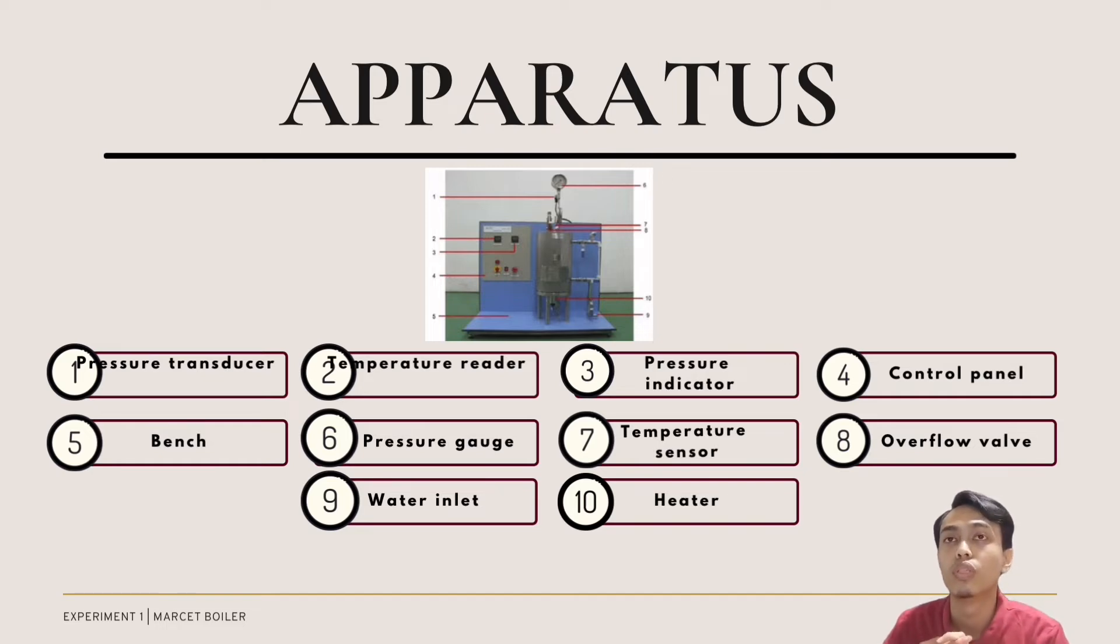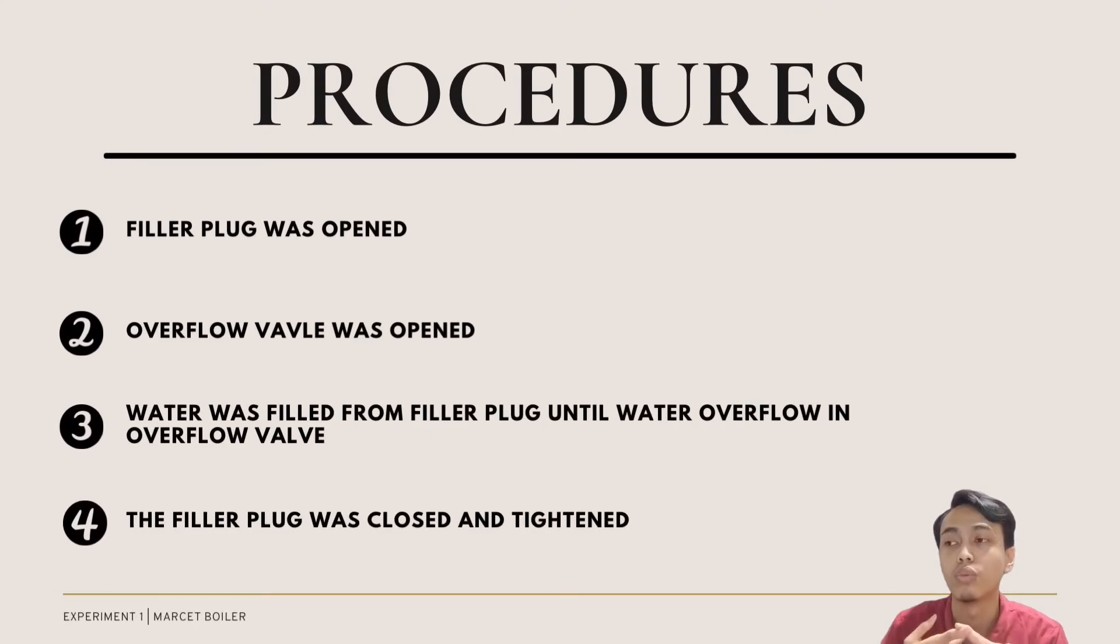Then, we move to the procedure. The first step: open the filler plug with the spanner. Second, open the overflow valve. When both are open, fill the water from the filler plug until the water overflows in the overflow valve. Once the water overflows in the overflow valve, close the filler plug and tighten it.